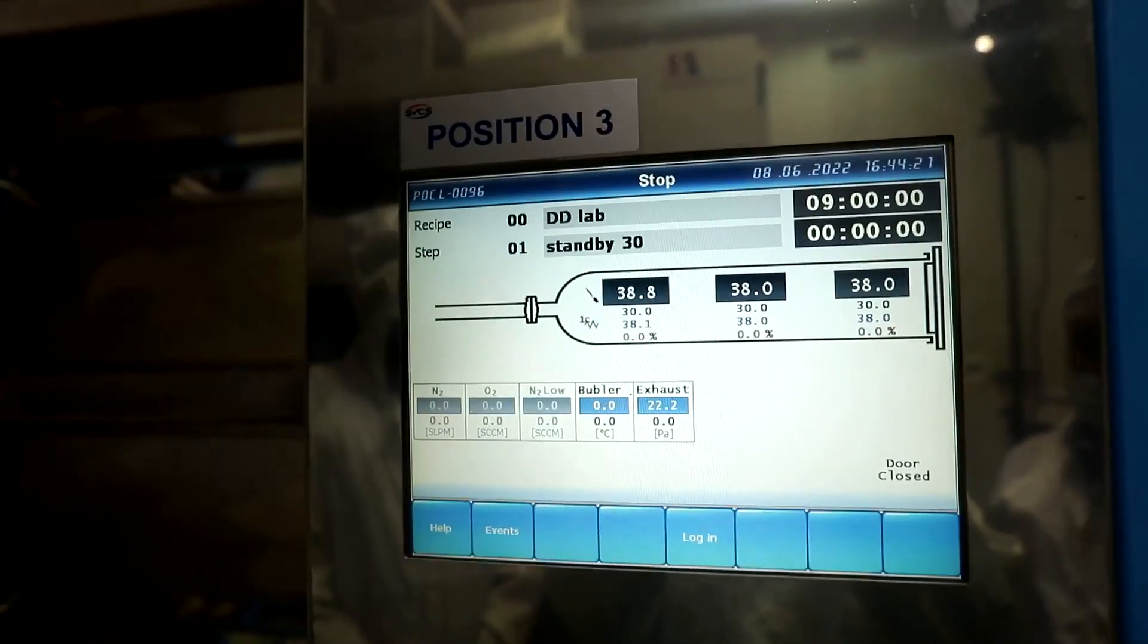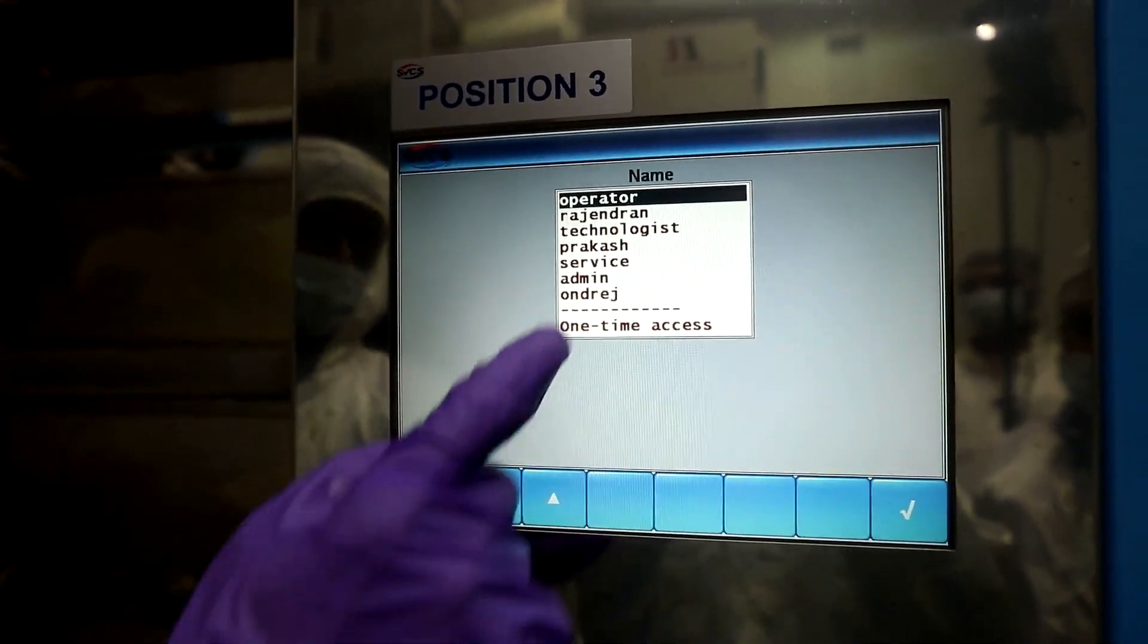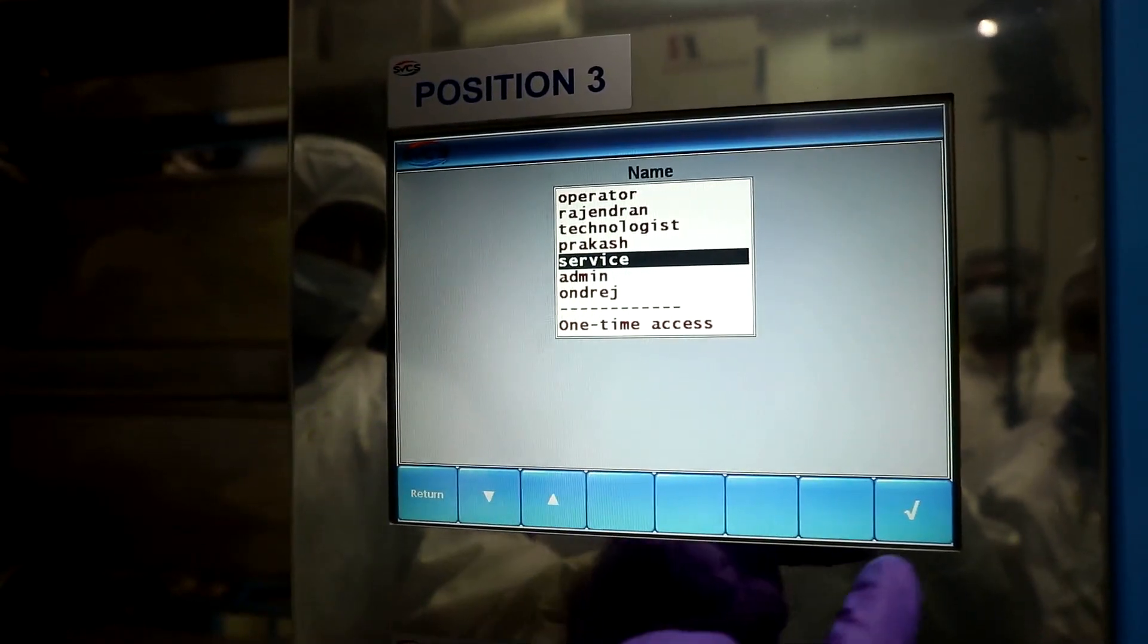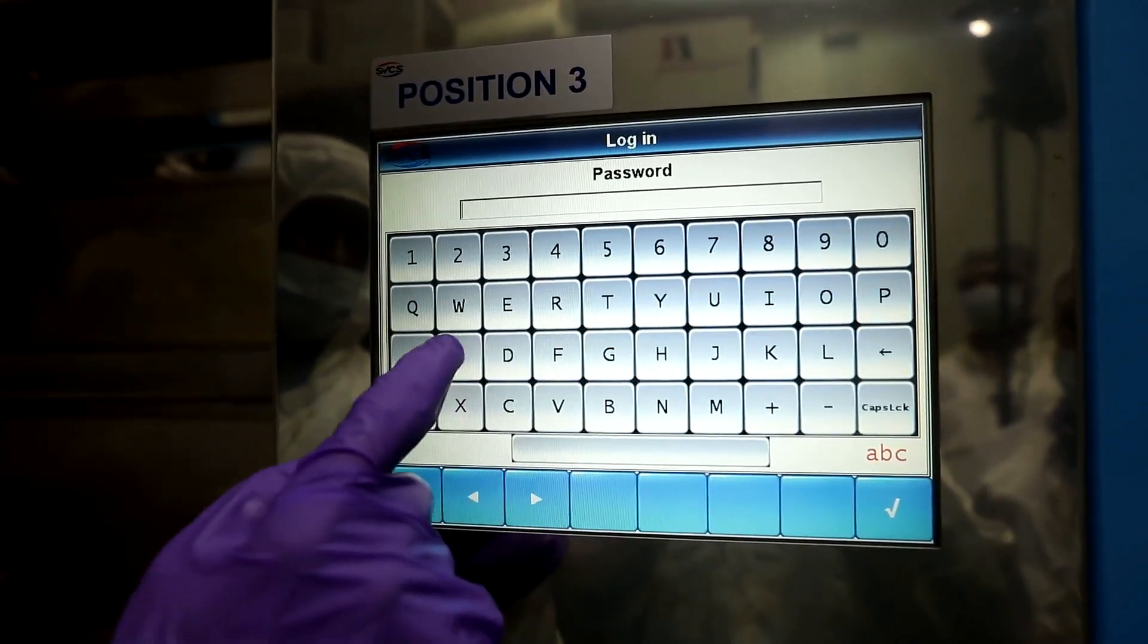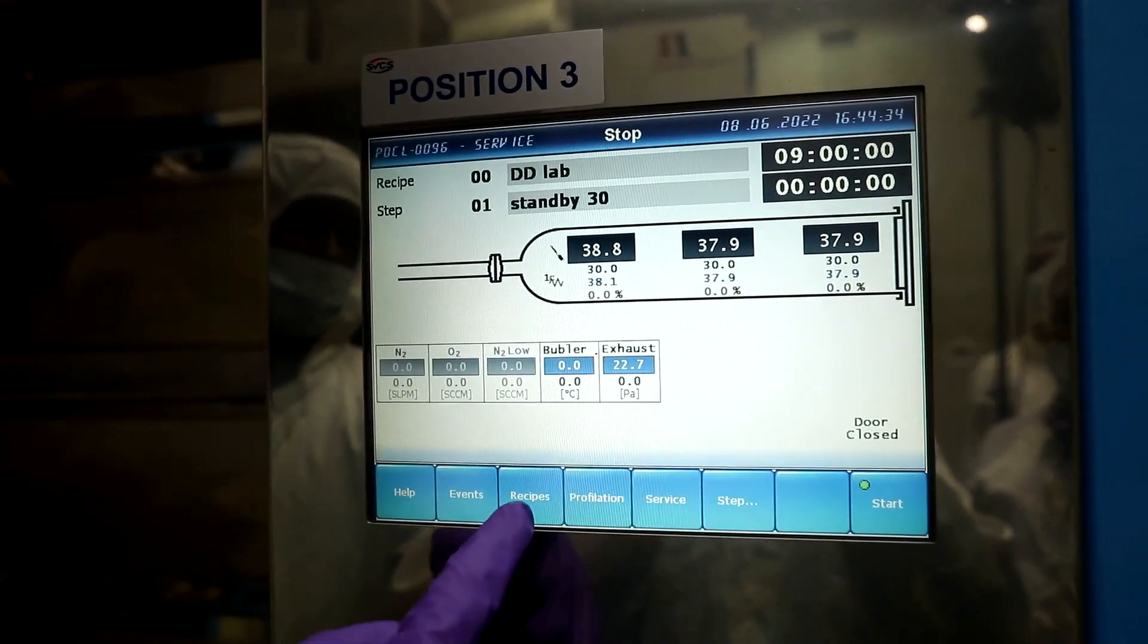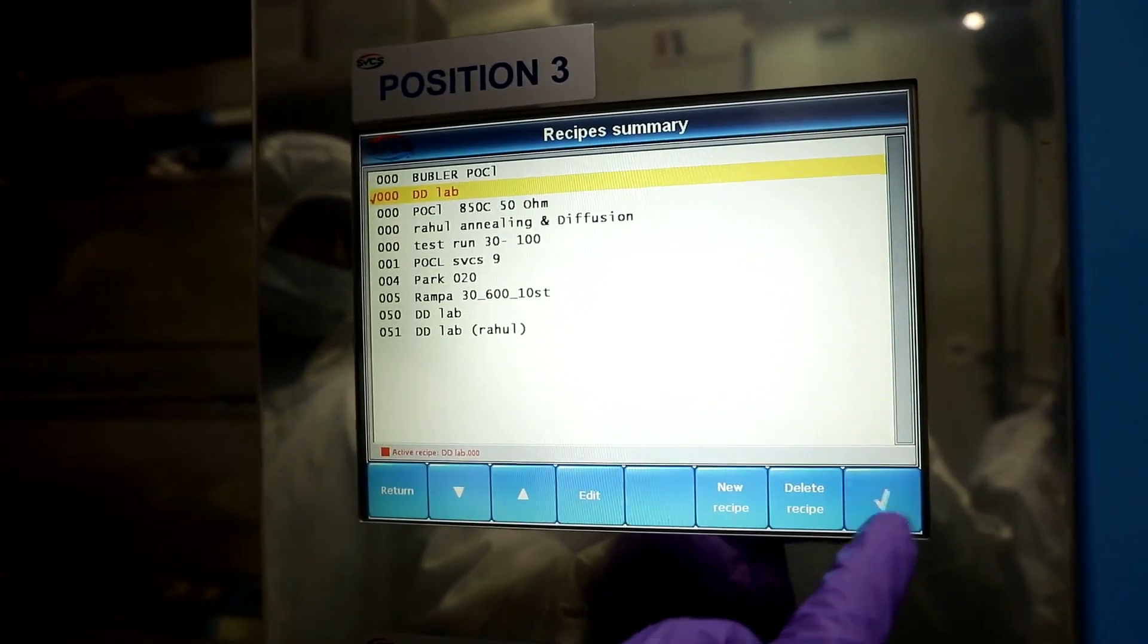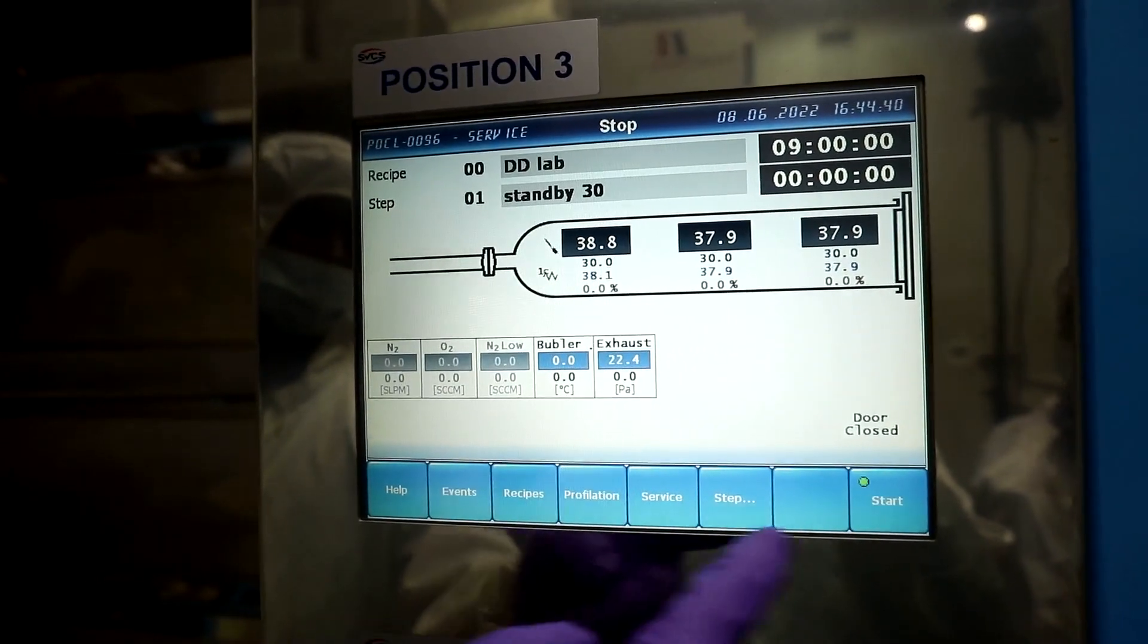Now when the display shows all open, we will open the phosphorus diffusion display. Go to login and press the service mode and enter the password. Now let us open the phosphorus diffusion process sequences. It contains all processing steps. We need to check process parameters here.